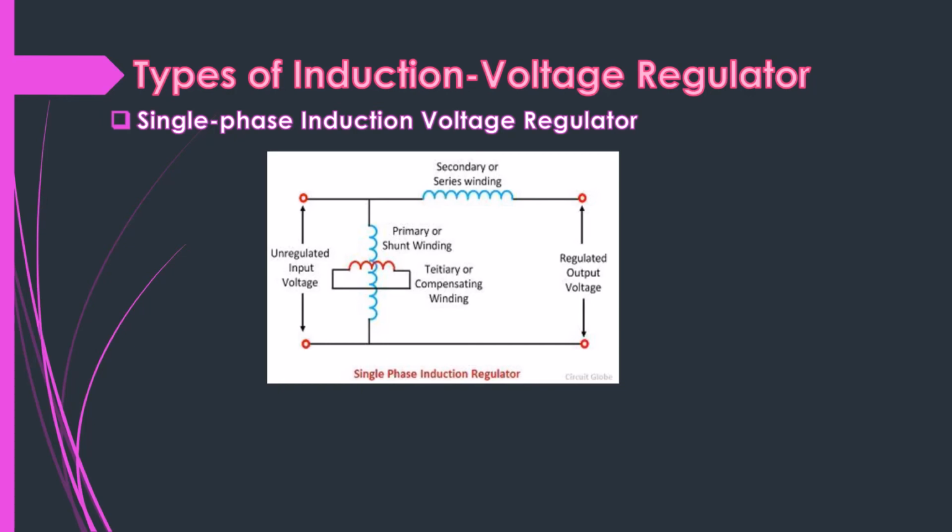The primary windings are placed in slots in the surface of the laminated cylindrical core since they have to carry small currents and need a small conductor area. The magnetic axis of the compensating winding is always 90 degrees away from that of the primary windings to neutralize the harmful series reactance effect of the secondary. The secondary windings, connected in series with the outgoing line, are housed in the stator slots due to their large conductor area.